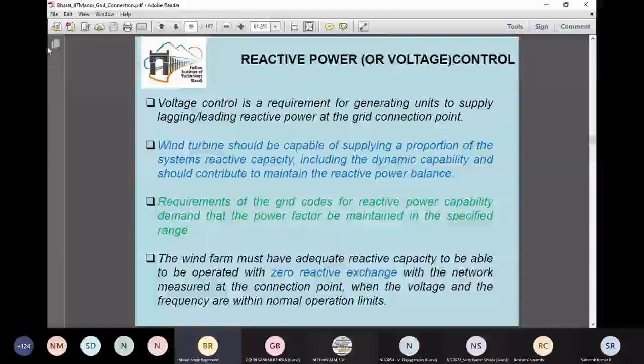So this is what the reactive power connection requirements are. Other than this, another requirement for voltage control or reactive power control is that a reactive power capability curve also needs to be provided to the transmission system operator, so that an operating point is available to the operator, showing how much margin is available for active power and reactive power feeding into or absorption from the grid. So this is what is expected. Next slide, please.